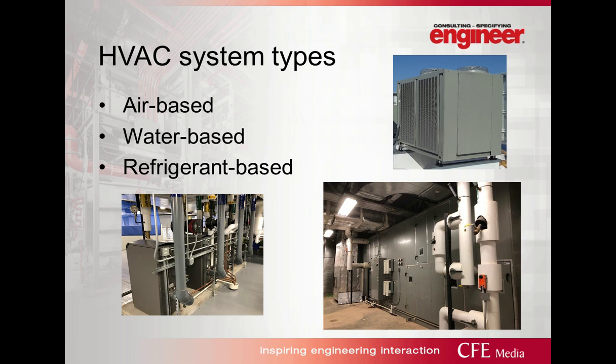I'm very excited to talk to you today about HVAC system design. Our broad range of attendees requires us to go through some basic steps before we dive too deep into selecting and designing HVAC systems. The first step will be to talk about different HVAC system options for buildings. The most straightforward system is air-based, typically achieved using package rooftop units — equipment with package direct expansion cooling, condensers, supply fan, and a heating medium of electric or gas. Other more sophisticated package rooftop units might have steam or hot water, as well as chilled water options.